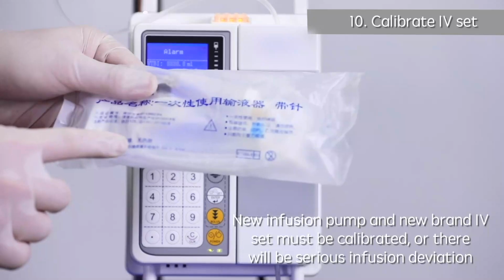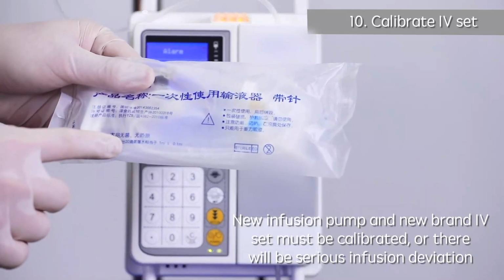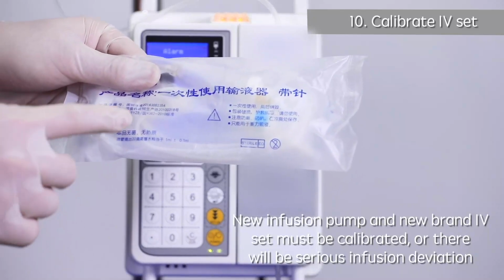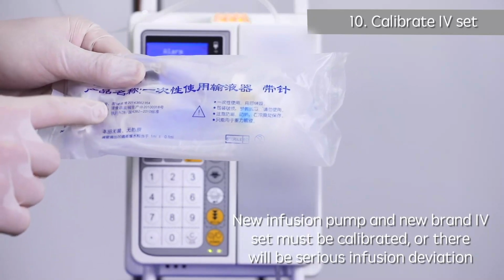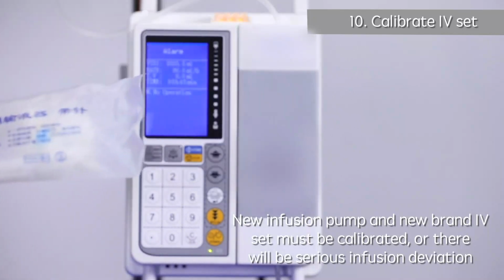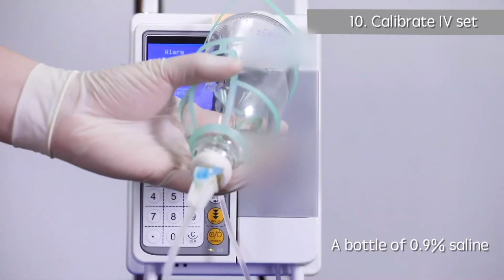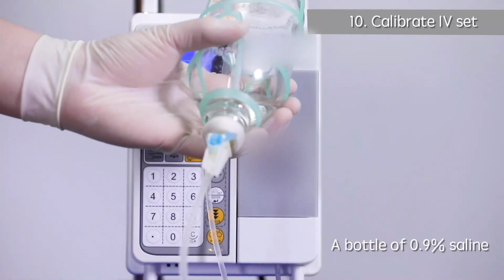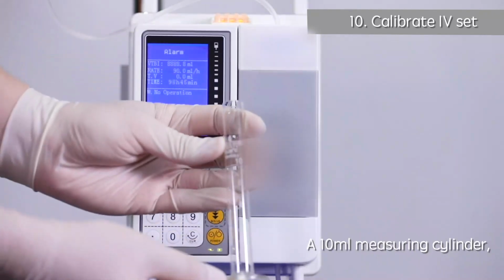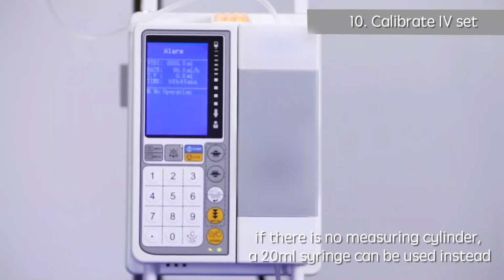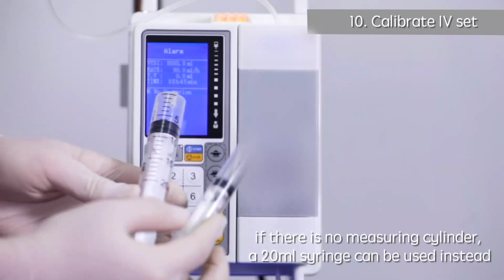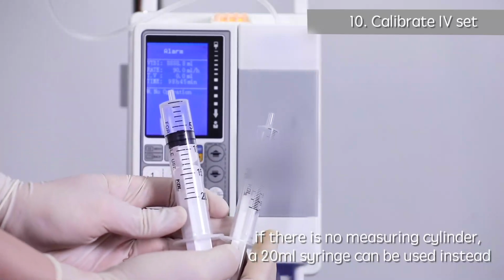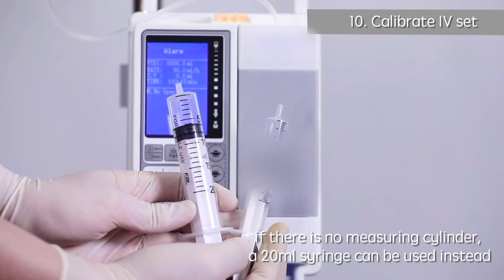Calibrate IV set. A new infusion pump and new brand IV set must be calibrated, or there will be serious infusion deviation. Prepare an IV set to be calibrated, a bottle of 0.9% saline, and a 10 ml measuring cylinder. If there is no measuring cylinder, a 20 ml syringe can be used instead.